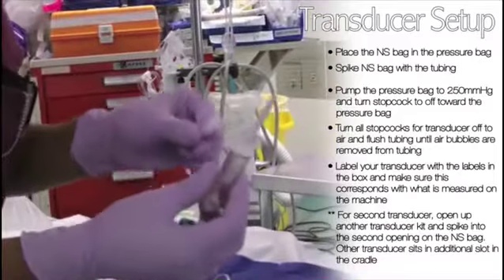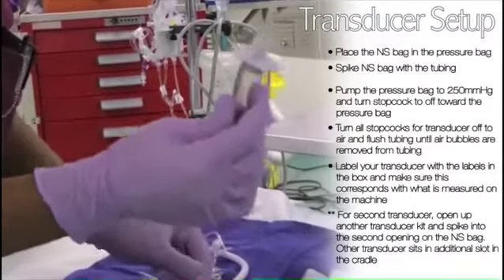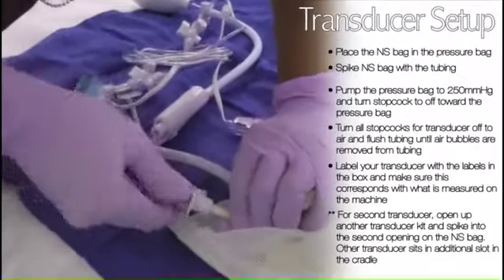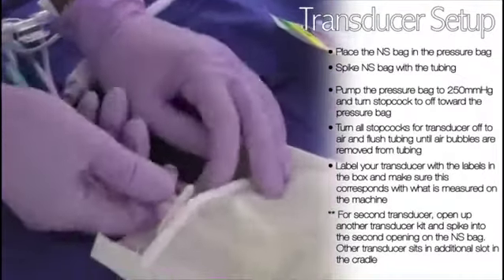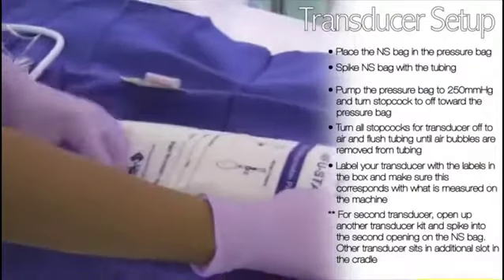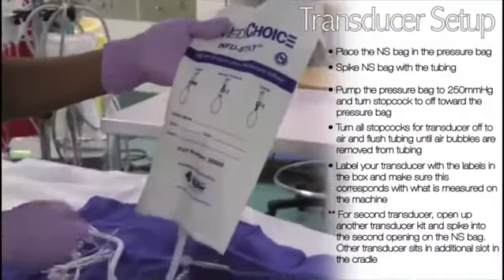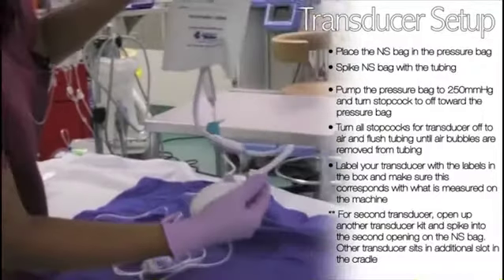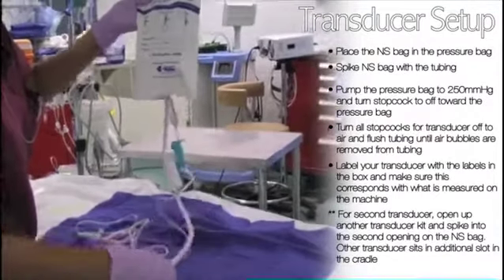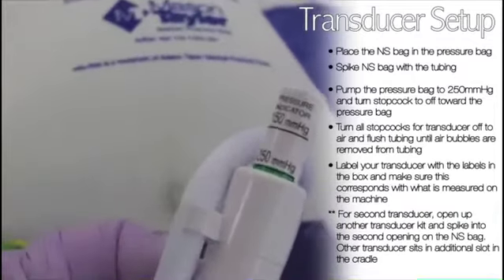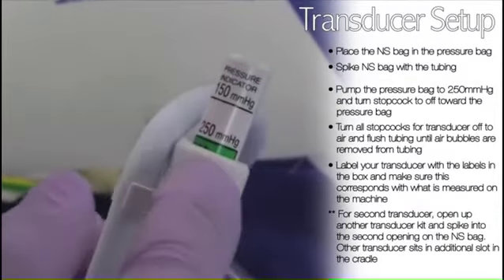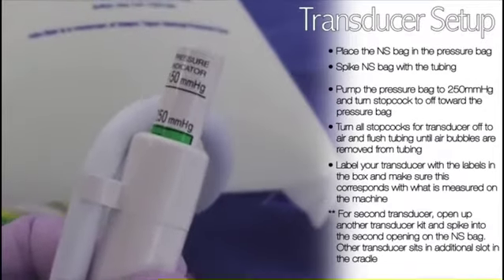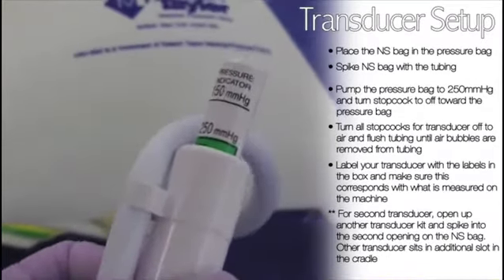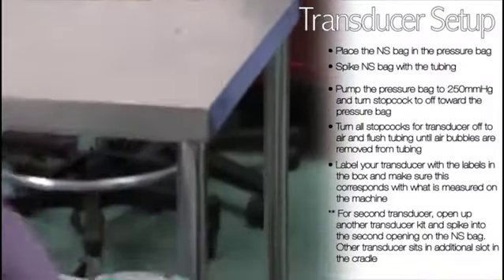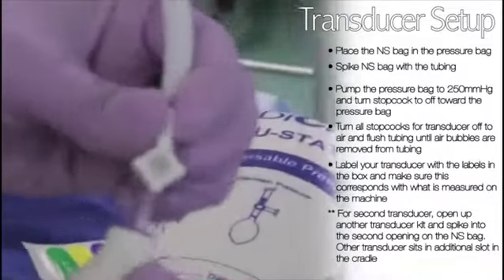Remove the plastic sheet that covers the insertion site. This has to remain sterile. And spike the bag. Once spiked, this pressure bag can now be inflated. To inflate, this needs to be off to air. A little bit above 250 millimeters of mercury, you'll notice that the pressure bag is adequately inflated. To make sure it stays maintained, the stopcock must now be off to the pressure tubing.